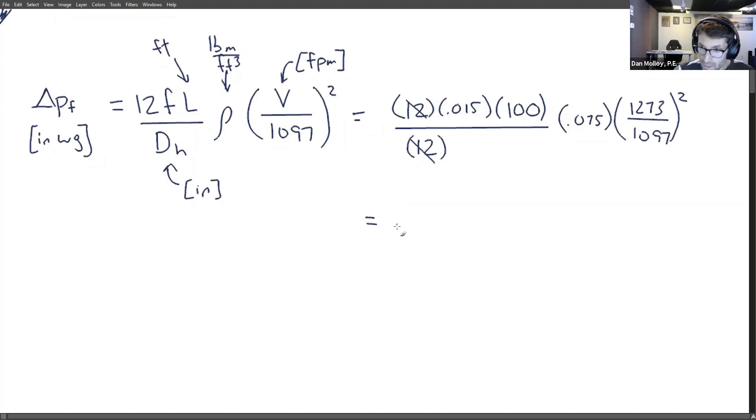And if all of those things happen, I'm getting 0.151 inches water gauge. And again, that's per 100 feet. If we exclude this term, this 100 feet here, then we would get the pressure loss for one foot.